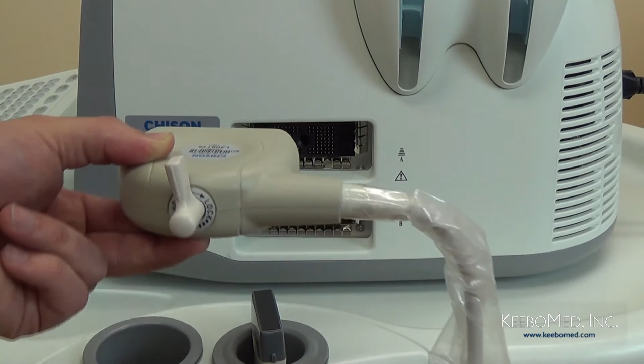Step number 4. Make sure that the probe cord is facing toward the back of the machine and horizontally insert the probe connector into the probe socket. Hold the probe connector and turn the lock knob to the lock position. Step number 5. Check the probe and make sure it is securely connected.